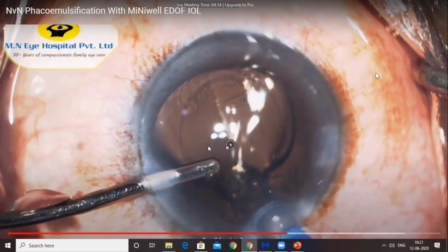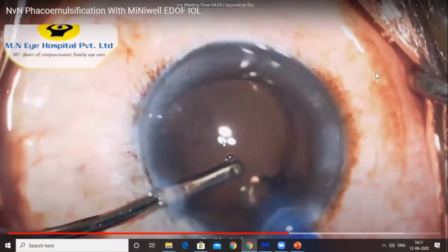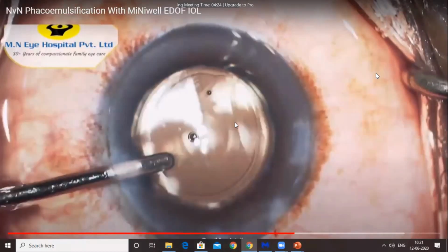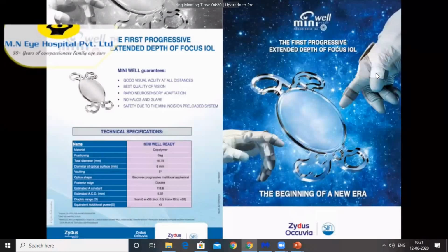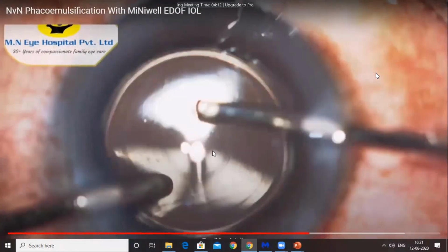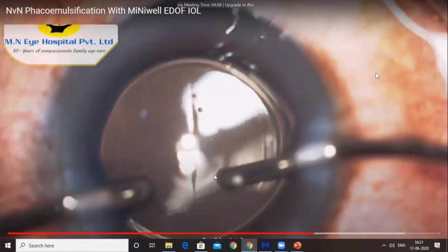inside the eye. This intraocular lens is based on a patented innovation which makes one continuous extended focus for sharp vision from far to near, going beyond what is currently possible with multifocal IOLs. The depth of focus is created by inducing targeted amounts of spherical aberration in concentric optical zones, generating a longitudinally extended continuous focal point.